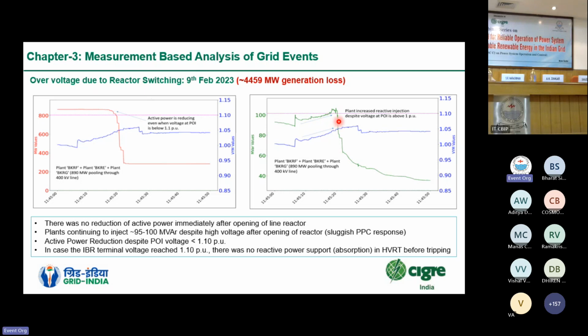The PPC response has been very sluggish in this case. And because of this gradual rise in voltage, we suspect that some of the inverters went into HVRT mode, and then there was tripping of some quantum of generation, which again led to the reduction of loading in the lines, and ultimately tripping of many IBRs in the vicinity. This is one of the cases where, if the PPC would have responded properly, we would have avoided this generation loss. Another observation is that the voltage was well below the HVRT limits. Even then, some of the IBRs tripped, maybe because of higher voltage at their respective terminals.